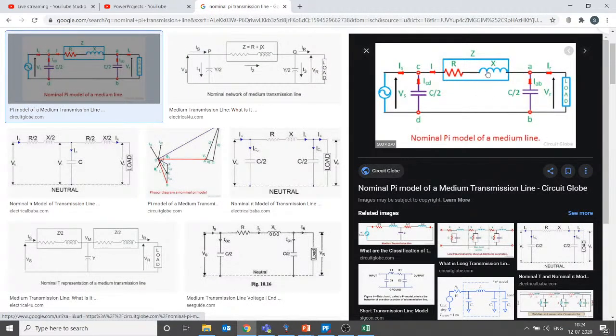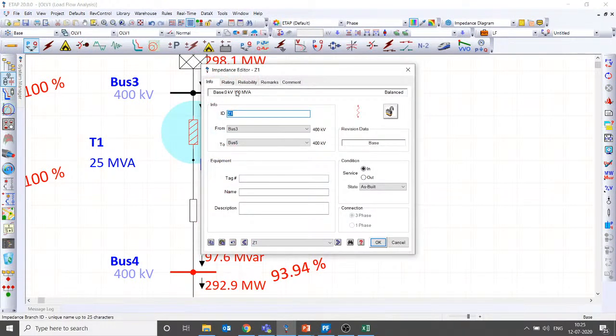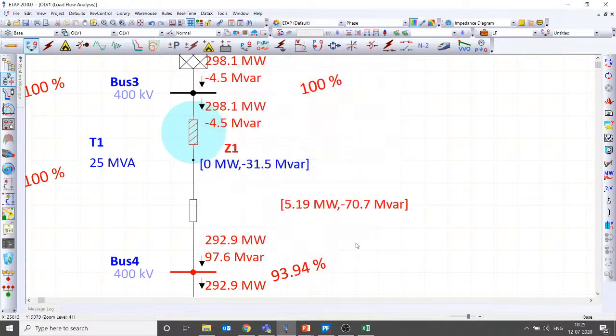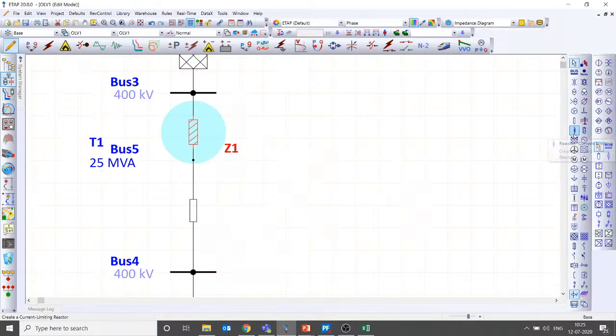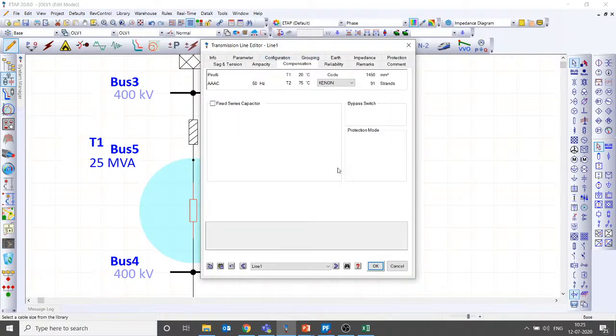If you have a long transmission line, this line reactance has a crucial role to play: it limits the power transfer capability and increases the voltage drop. You might be aware of the formula P equal to EV by X into sine delta. As the line length increases, the line reactance increases, and that reduces the power transfer capability. In order to compensate this line reactance, we are adding a series capacitance. That could be either fixed series compensation or a thyristor controlled series compensation. You don't have the option to play with thyristor controlled series compensation, but at least you can model this fixed series compensation here by adding a negative value in the impedance, or you have an option to compensate using an option compensation, right?